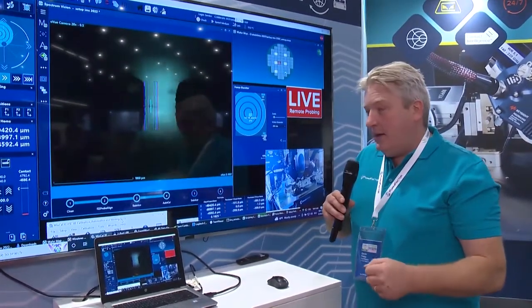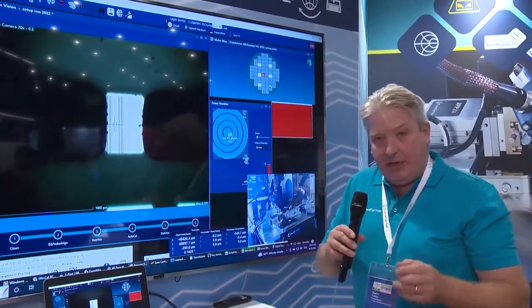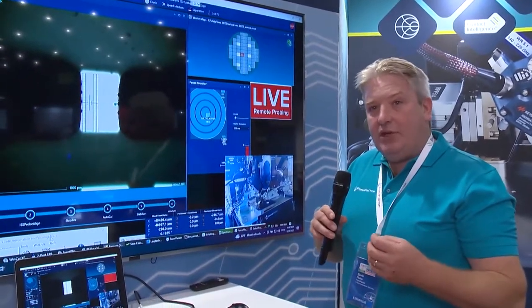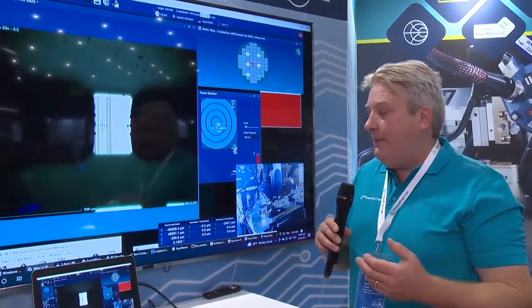probes back up. And then once this is complete, we'll run a validation and a monitor. So basically we're going to go grab the monitoring data from it. The monitoring data will be used to make sure that we know the calibration is still good at a later time. Why do we do this? Well, the systems do basically drift as a function of time, and we want to know that any measurement that we make is a valid measurement.